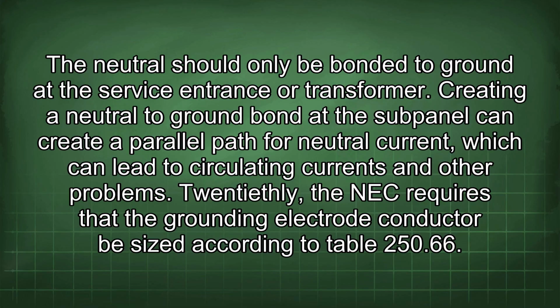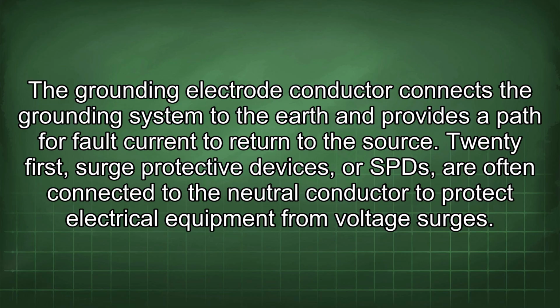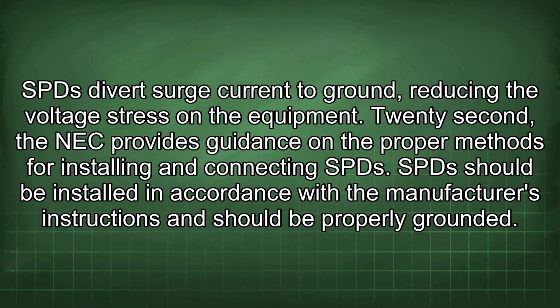20thly, the NEC requires that the grounding electrode conductor be sized according to Table 250.66. The grounding electrode conductor connects the grounding system to the earth and provides a path for fault current to return to the source. 21st, surge protective devices, or SPDs, are often connected to the neutral conductor to protect electrical equipment from voltage surges. SPD diverts surge current to ground, reducing the voltage stress on the equipment.